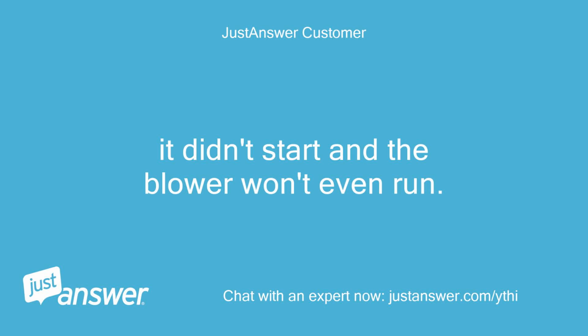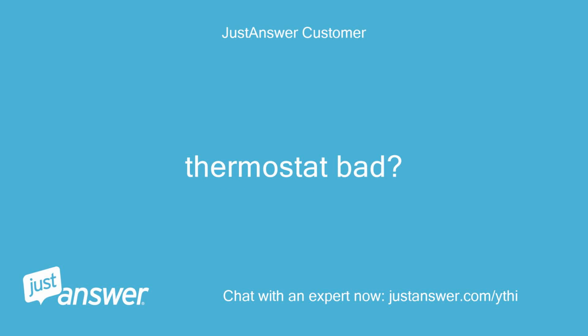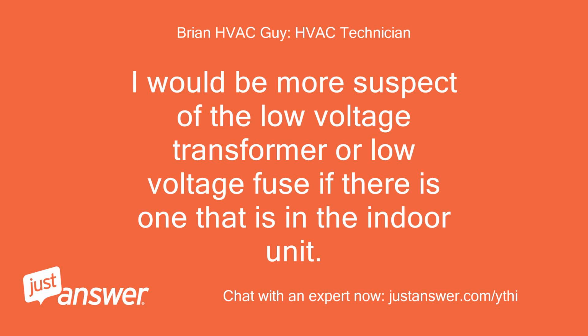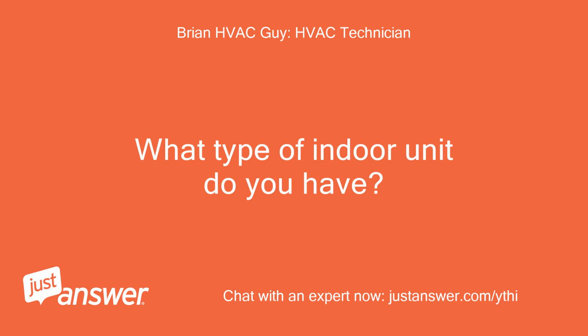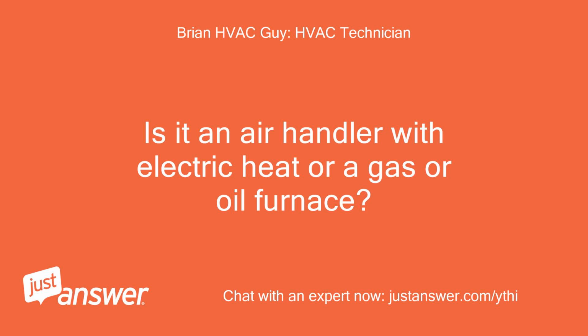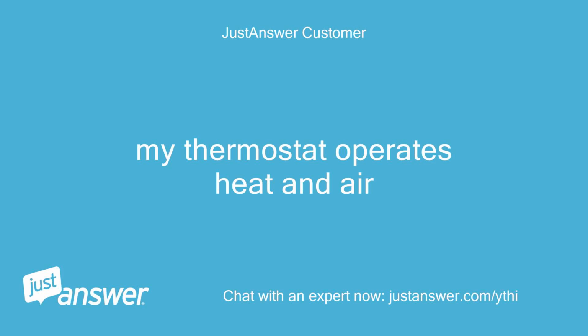It didn't start and the blower won't even run. Thermostat bad. I would be more suspect of the low voltage transformer or low voltage fuse if there is one in the indoor unit. What type of indoor unit do you have? Is it an air handler with electric heat or a gas or oil furnace? My thermostat operates heat and air.